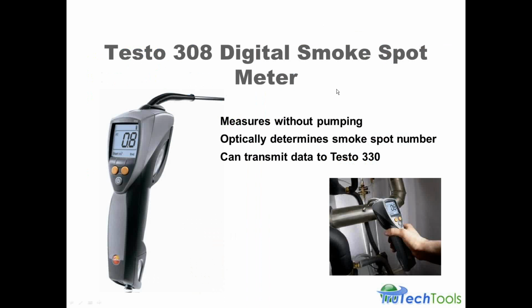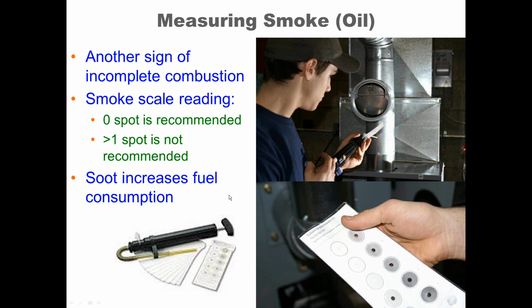We did want to make sure you're aware that Testo does have a digital smoke spot meter. On the last page here, we're talking about the manual smoke spot. Testo and Bacharach both make one. Bacharach was one of the originators of this, and the scale for it, the Shell Bacharach scale, where you actually pull a gas sample with something similar to a bicycle pump, but you pull it through a filter material and then read it up on a scale to see what level of soot you have, the smoke spot.